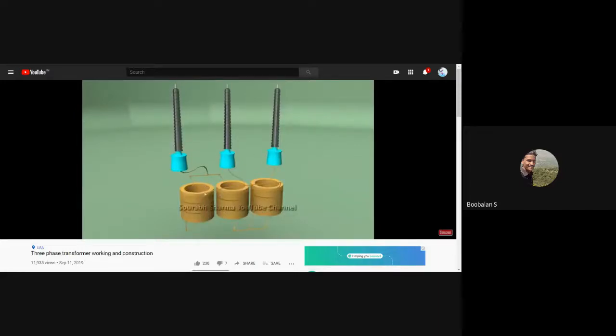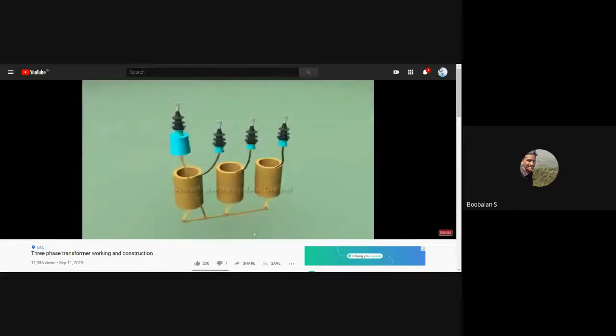Here in these two coils, the upper ends of each coil are connected at a common point and connected to a bushing. The lower ends of these two windings are connected at a common point and brought out through this bushing. And at last, the lower end of the first coil and the upper end of the third coil are connected together and brought out through this bushing. In this way, the high voltage winding is connected in delta.